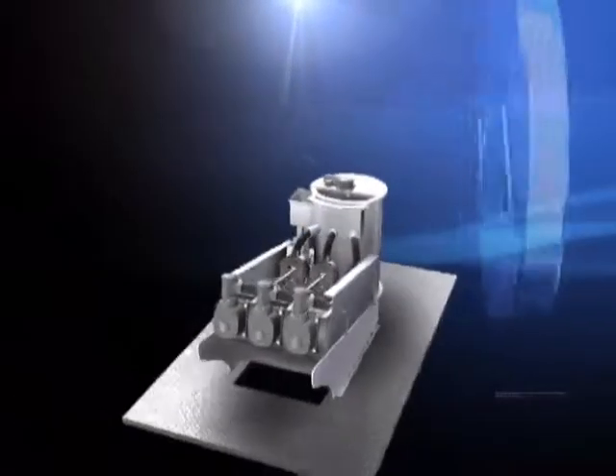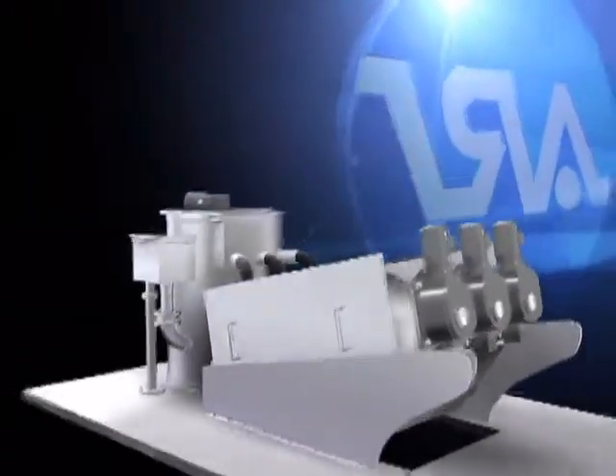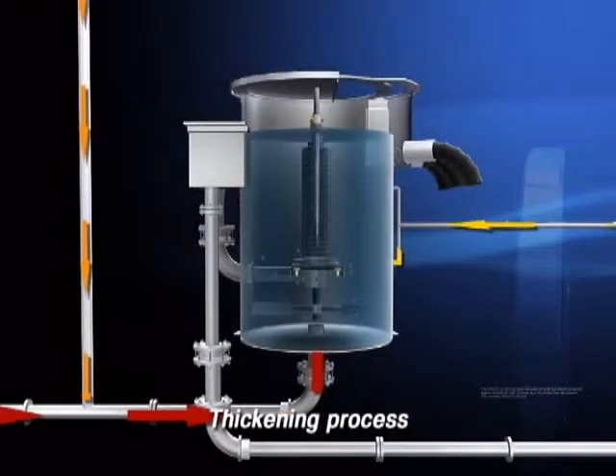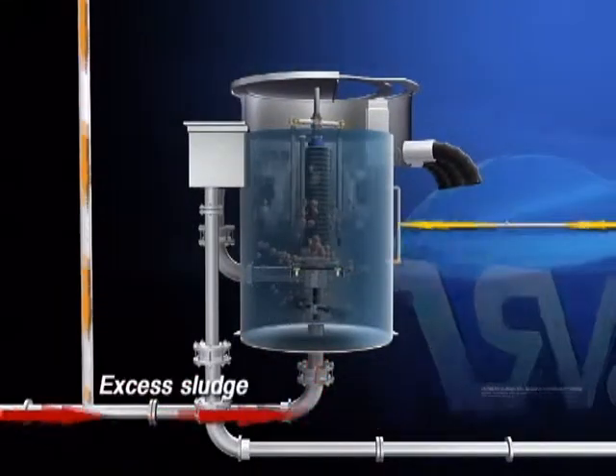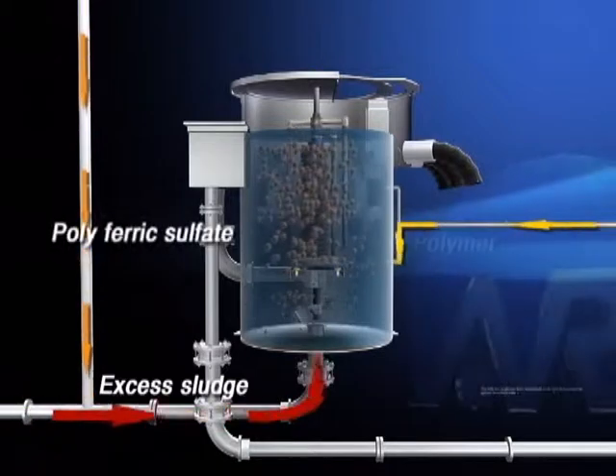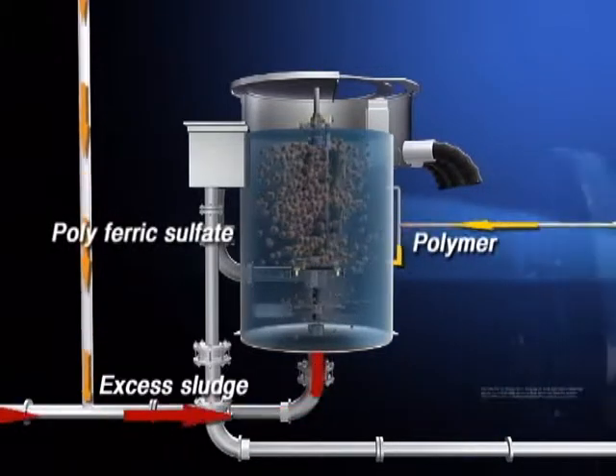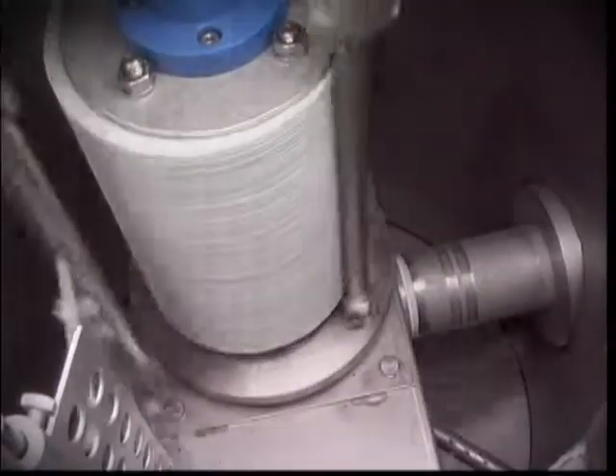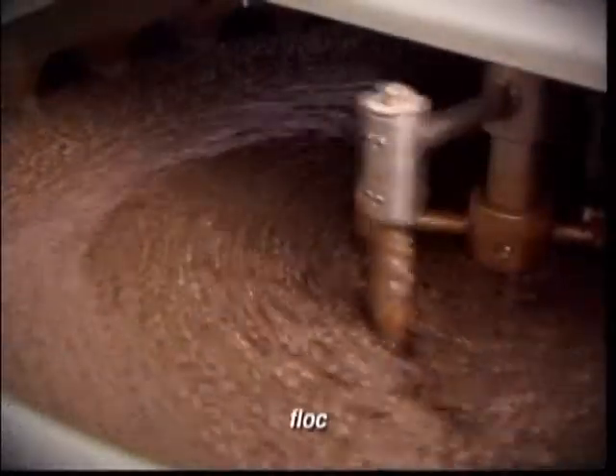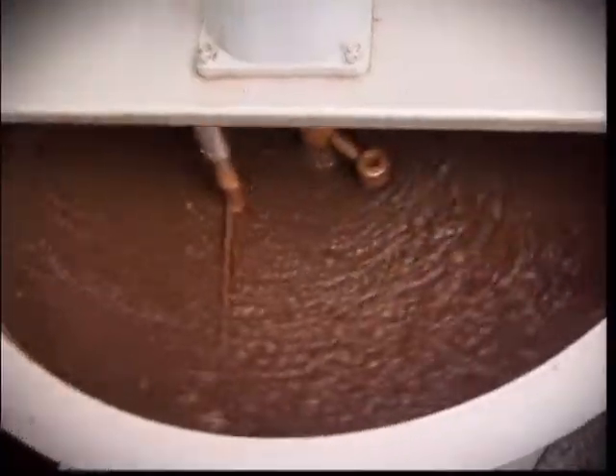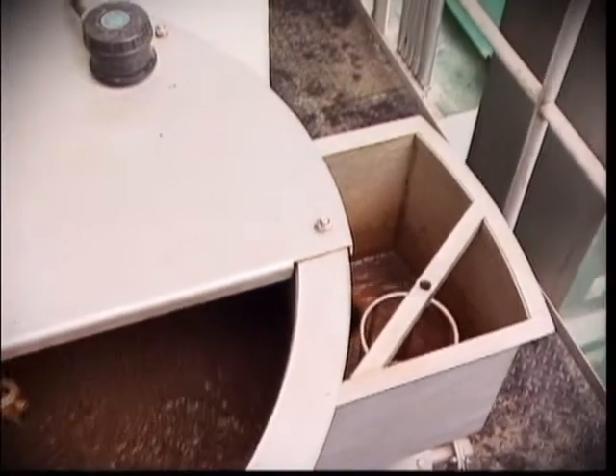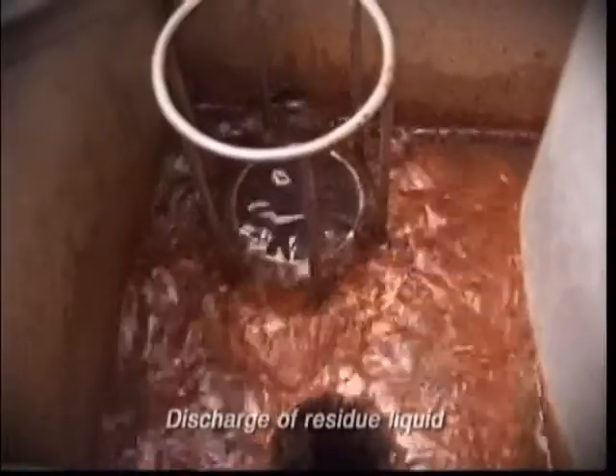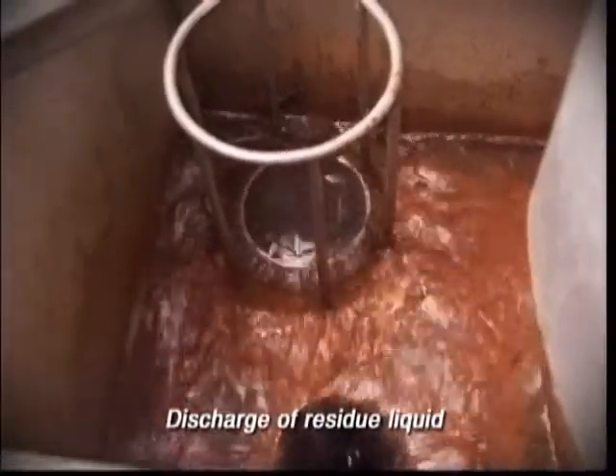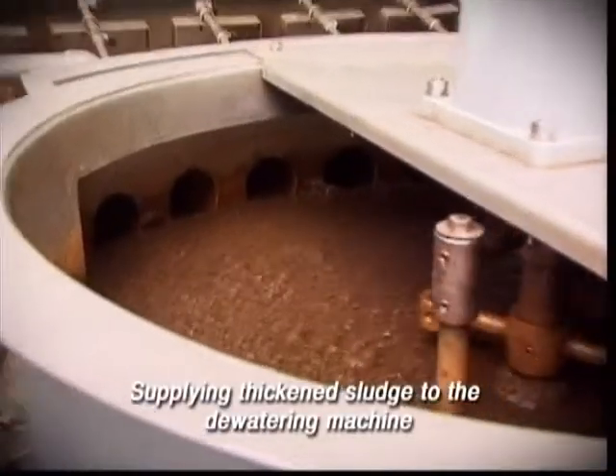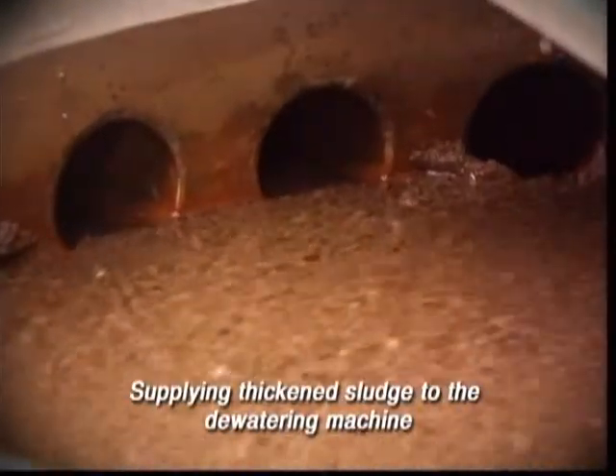Let's look at how our thickener and multiplex plate dewatering machine processes sludge. Sludge is first combined with polyferric sulfate and polymer to form flocks during the concentrating process. The flock is concentrated as residual liquid is separated from the sludge by the residue discharge device. The residual liquid is returned to the early treatment plant, and the thickened sludge is brought to the dewatering machine.